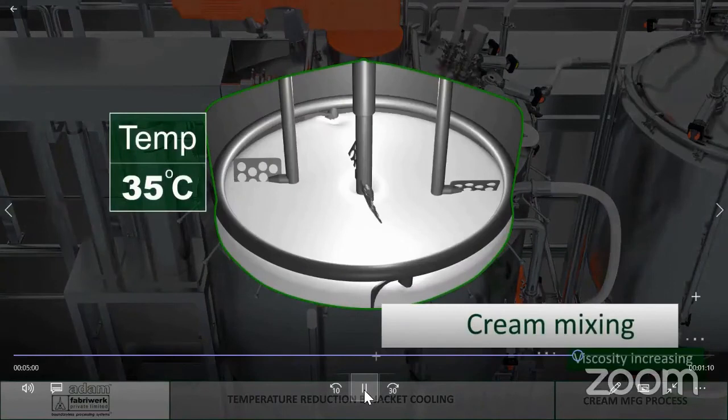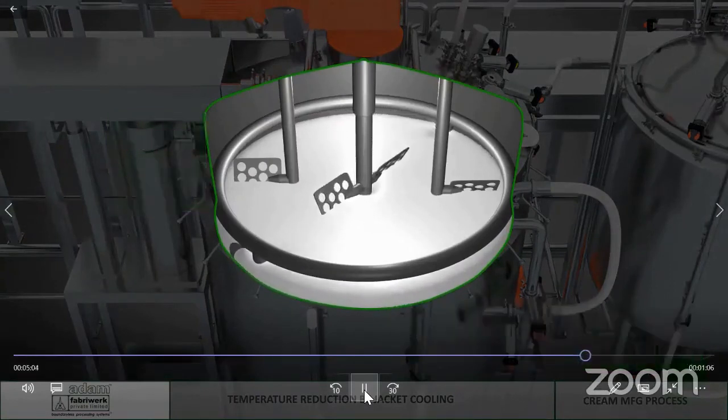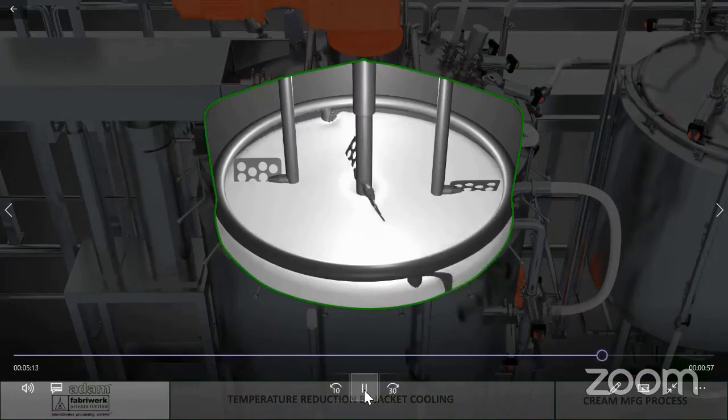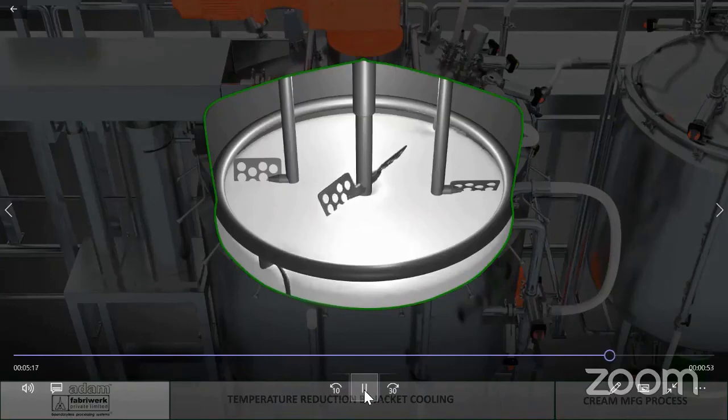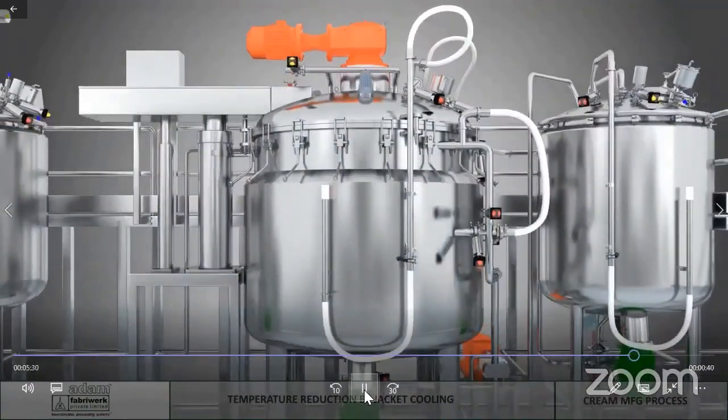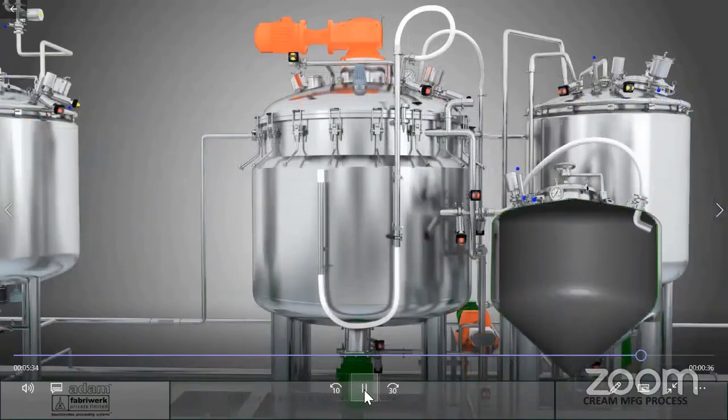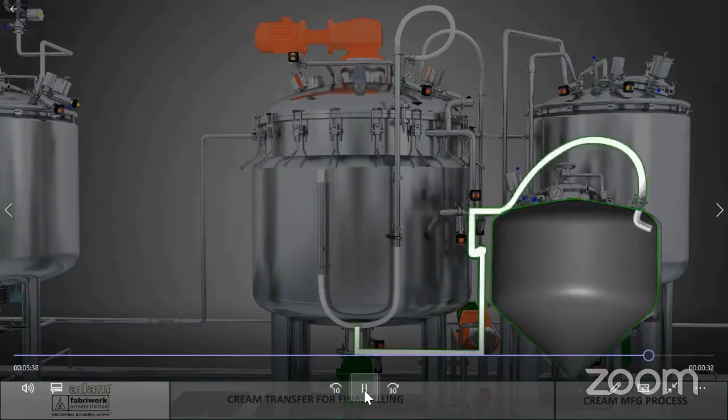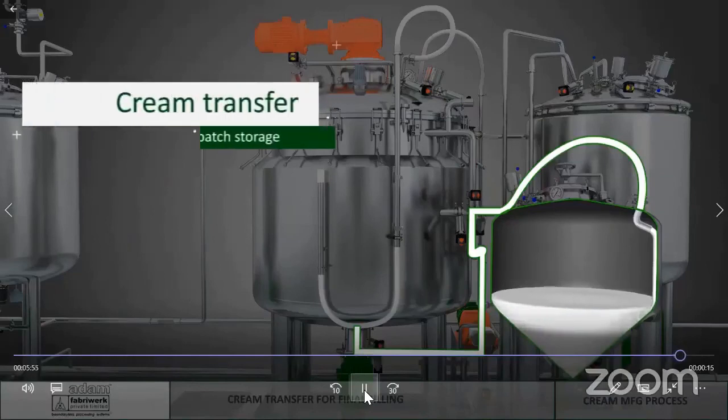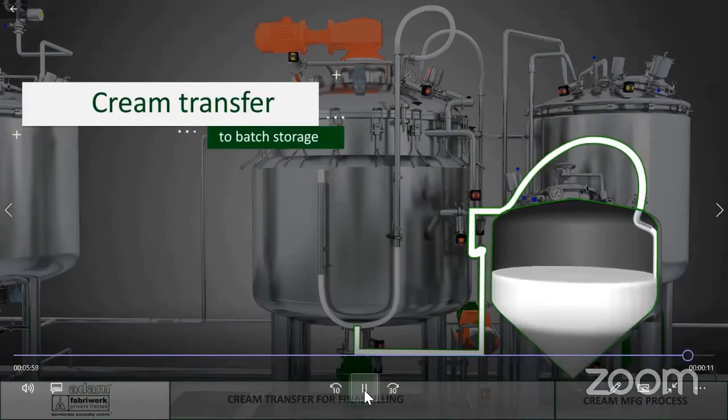The complete system moves through a series of automation cycles of modular operations of vacuumizing, mixing, checking the weight, and then the high shear as well as the transfer to ensure that the product that is made is compliant to the recipe cycles that have been designed by the R&D team and pilot operations. The same scale can be scaled down from a larger batch size to a lower batch size of 50 kilos and can be manufactured in an R&D batch size of 5 kilos, and this can be scaled up all the way to 1000 kilos or 10,000 kilos, essentially keeping the geometry and tip speed with the shear rates of the agitation system as a constant.